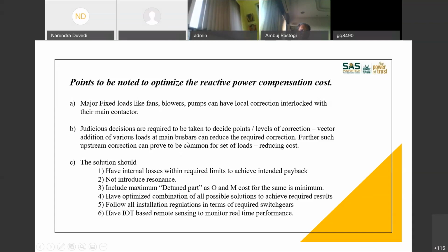This can be very neatly and correctly simulated on electrical system simulation software, and better solutions can be designed with a lot of confidence. I mean, there won't be thumb rule application as such, but you can get good solutions out of this. So actually, what should your solution have? It should have internal losses within required limits to achieve intended paybacks. It should not introduce any resonance to increase harmonic distortion. Include maximum detune part, as O&M cost for the same is minimum. Detune, or I would say passive.